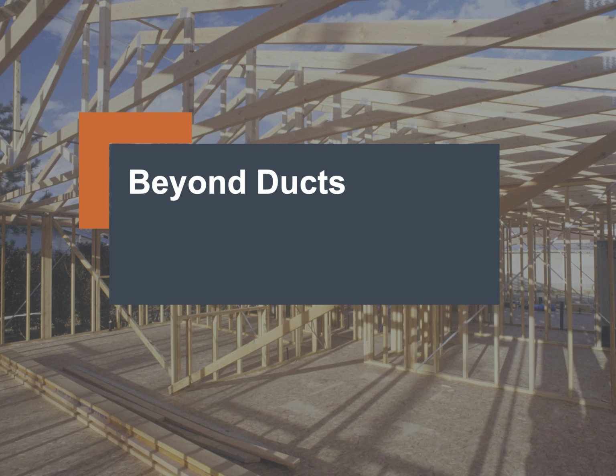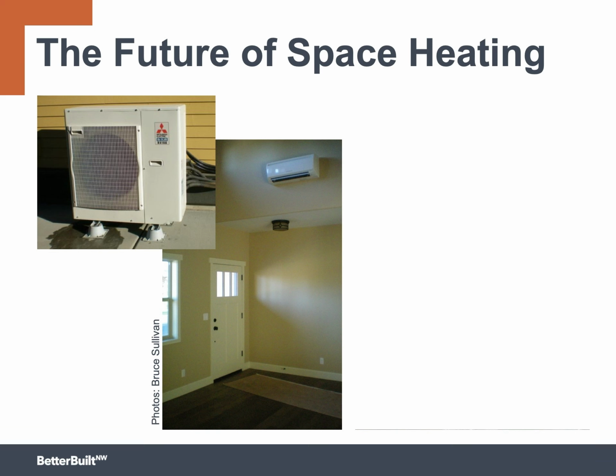We've been talking about placing ductwork inside conditioned spaces, but here's another thought. The purpose of a heating and cooling system is to keep people comfortable. What if that could be accomplished without ducts at all? This is possible in high-performance homes with very low heating and cooling loads. Mini-split heat pumps and furnace-rated fireplaces are two ways to totally eliminate duct issues for small, efficient homes. For smaller homes with open floor plans, complete comfort can be delivered without a traditional central heating system. Because modern houses have much more efficient building envelopes, there really isn't a need to deliver heating or cooling to each room. One option is a fireplace designed to be a heating appliance and not a decorative element.